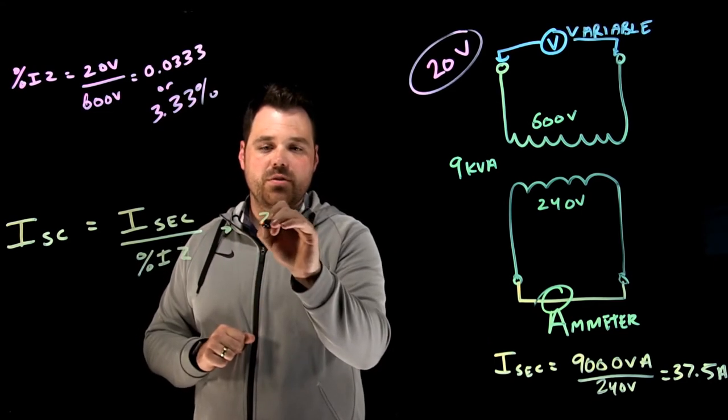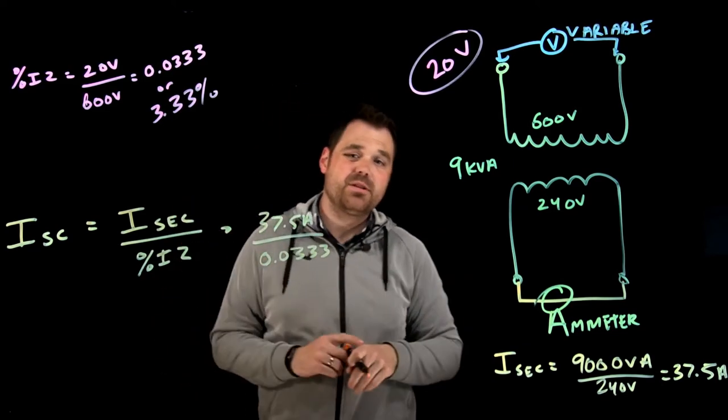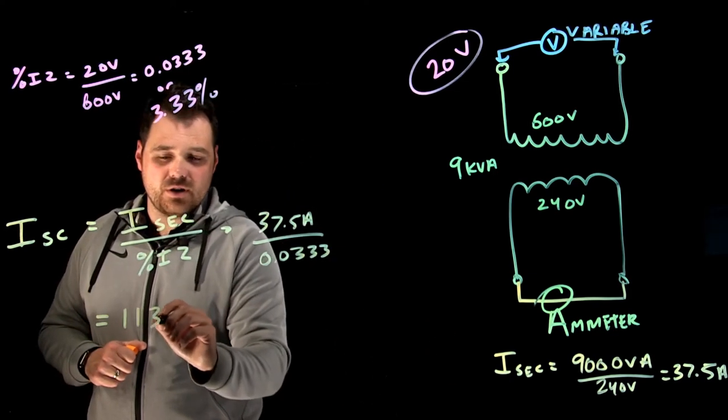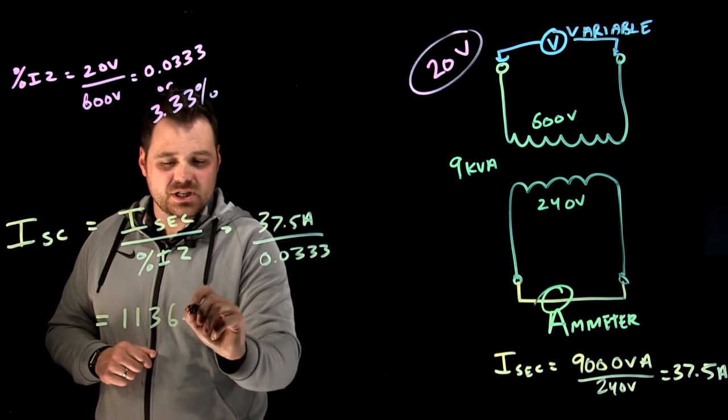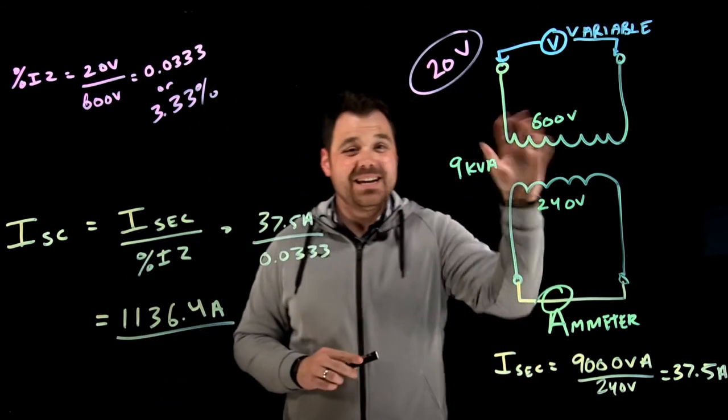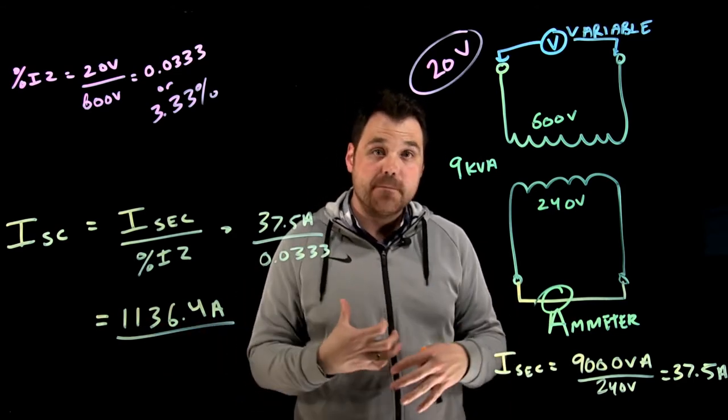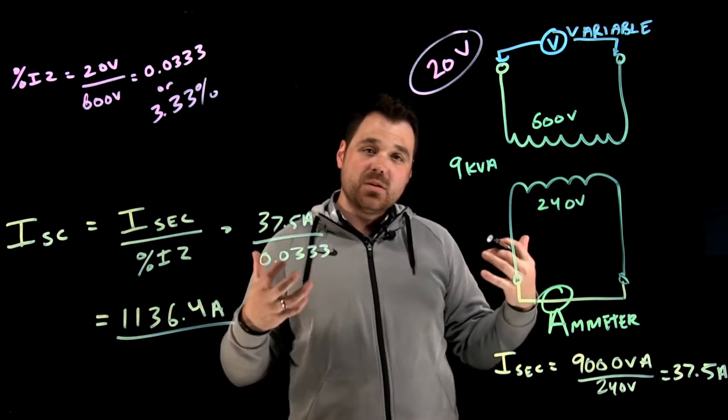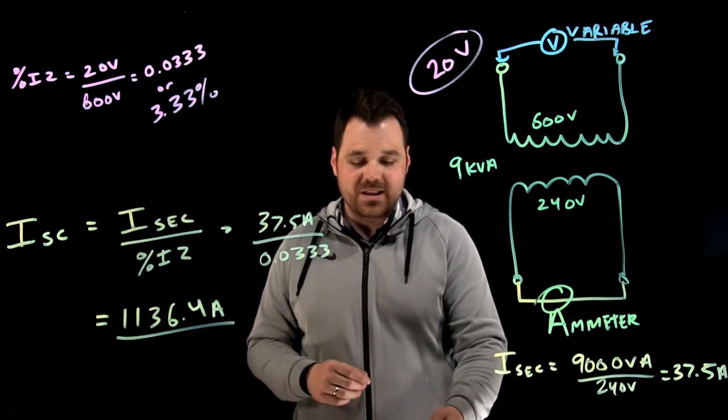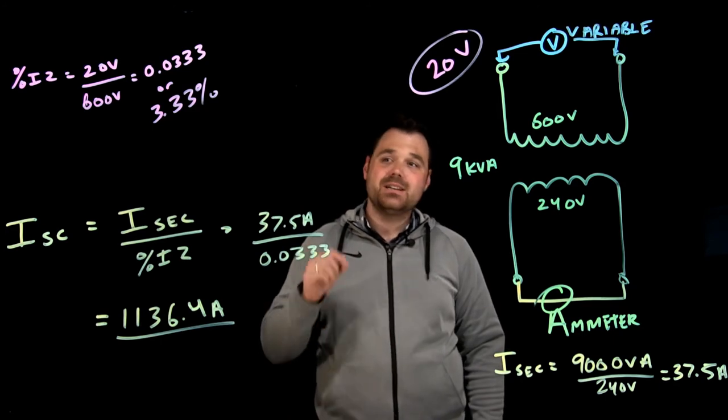So in this case, I'm going to go 37.5 amps divided by 0.0333 or 3.33 percent. That gives me my short circuit current. In this case, it's about 1136.4 amps. That is a huge number. This transformer, the impedance of the transformer is going to limit my short circuit current to 1136 amps. So the impedance of the transformer is all that's standing in the way. I know along with the impedance of my short circuit path, but that right there is what I have available as a secondary fault current on this transformer. That's one of the reasons that calculating this percent IZ can be so important.